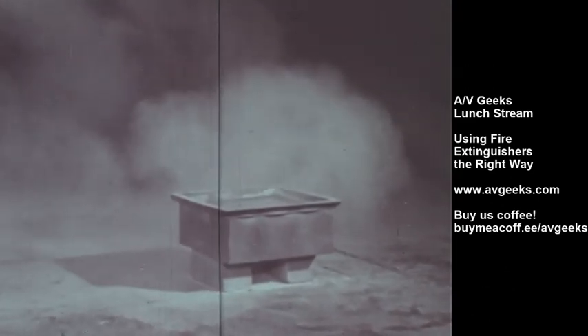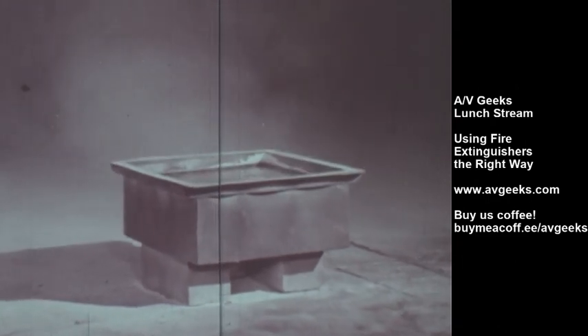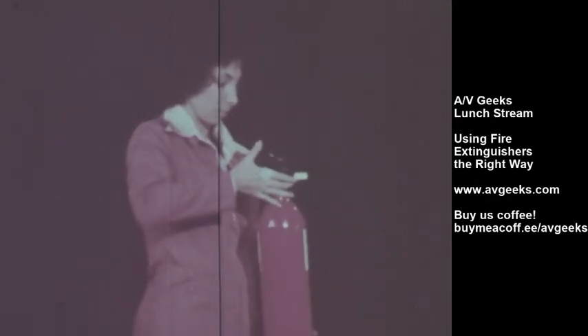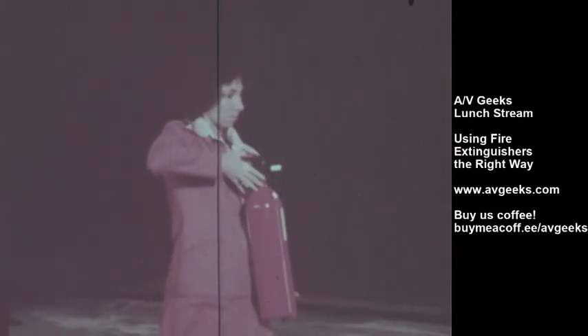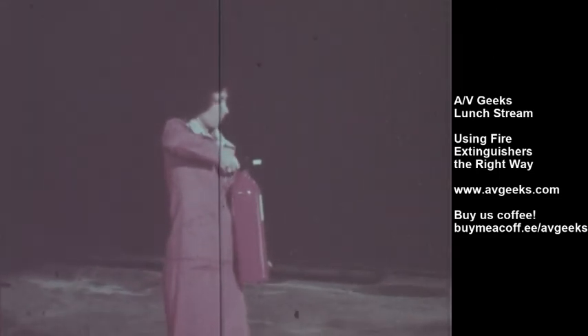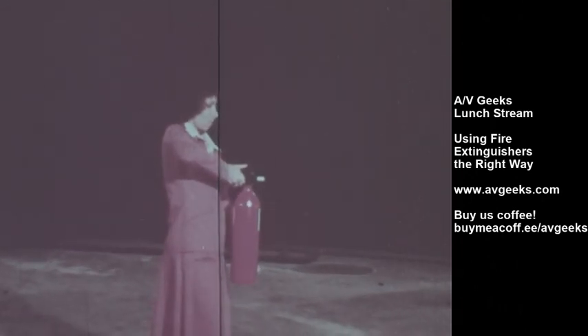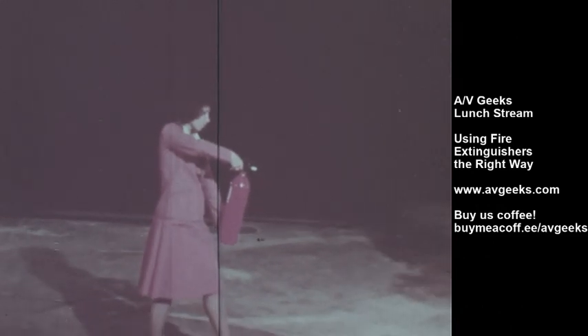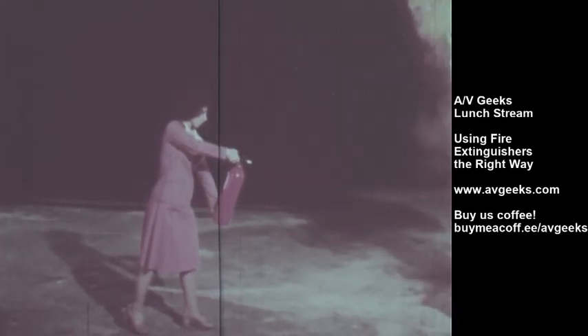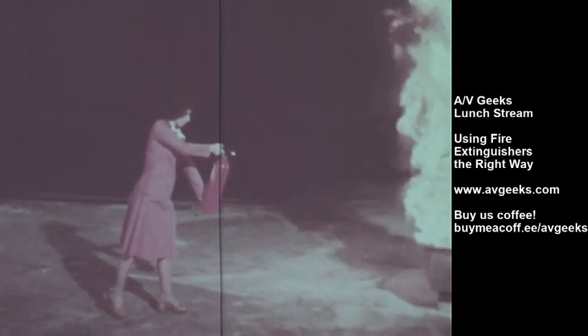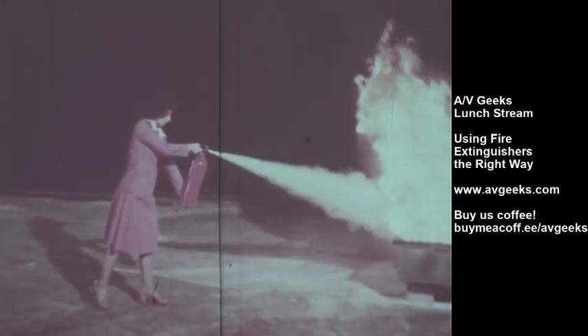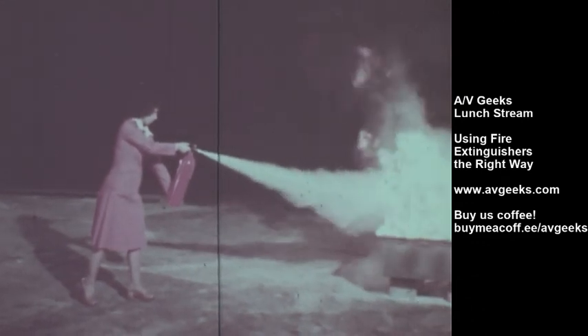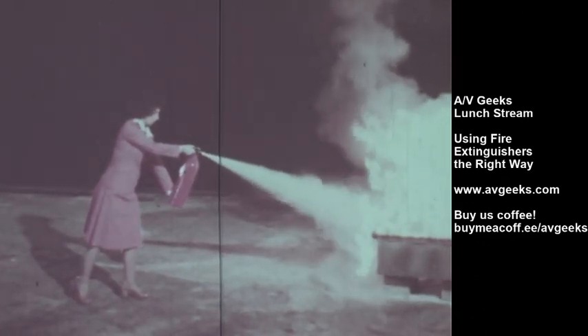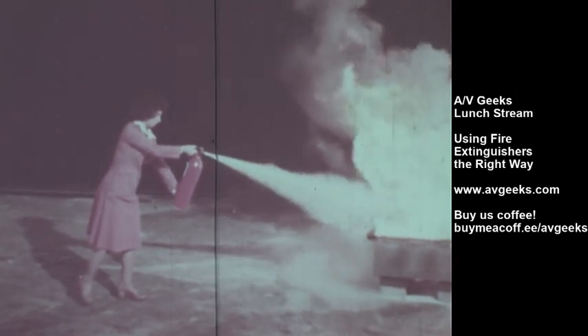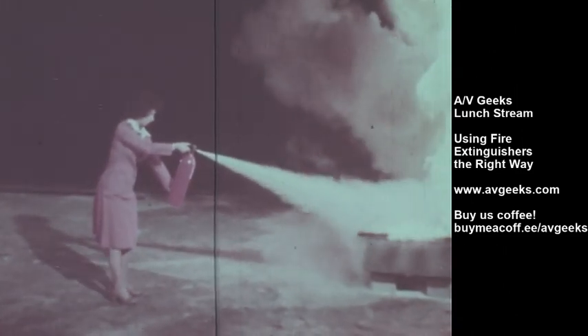Let's see how critical, this time more slowly. With a flammable liquid fire, it is particularly important how you approach and aim the extinguisher. The maximum range for a dry chemical extinguisher is 12 to 20 feet, much shorter than for the water extinguisher. After pulling the pin, aim at the base of the fire and squeeze the lever. Sweep the extinguisher from side to side, starting at the front edge of the fire. The discharge will last from 8 to 25 seconds, depending on the size of the extinguisher.